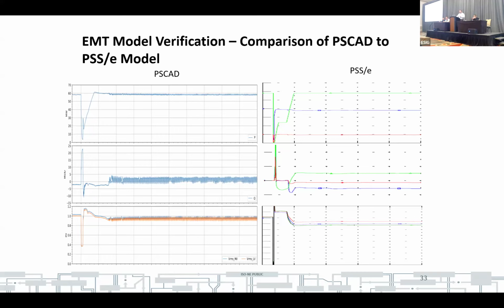One thing we're looking for in these benchmarks: we're never looking for an unbalanced disturbance to match well with, say, a PSSE model, because we know that's just not going to happen. And we're also not looking for an exact match, even with balanced type faults that may be identical between the two simulation domains. What we are looking for is a sort of average response to be very similar. And obviously it's always very subjective, but that's why we tend not to get into the weeds of how close is close enough.